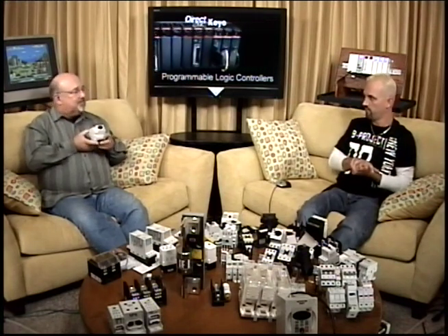In the next slide, we're showing a quick wiring diagram. We're showing the manual motor starter controlling the motor, and technically that's all we need. We have our protection and everything else, and in some applications that's all we would need. That's the simplest way of starting an electrical three-phase motor. Yep, but simplest and probably least expensive. But the only control you have is on or off. It's going to be full RPMs, full current, full voltage.